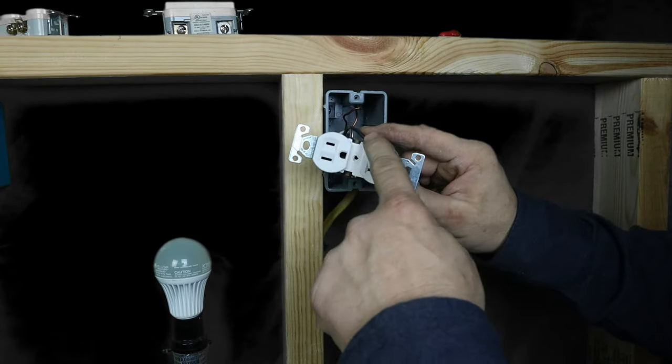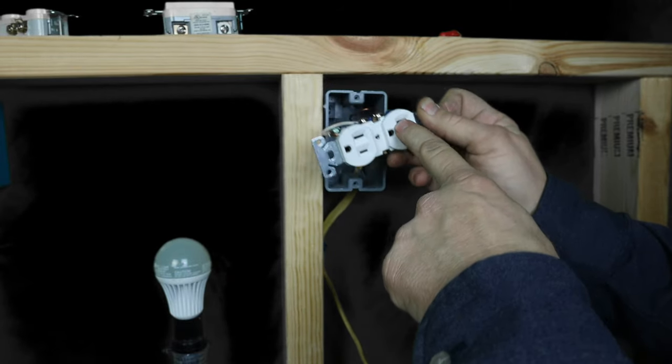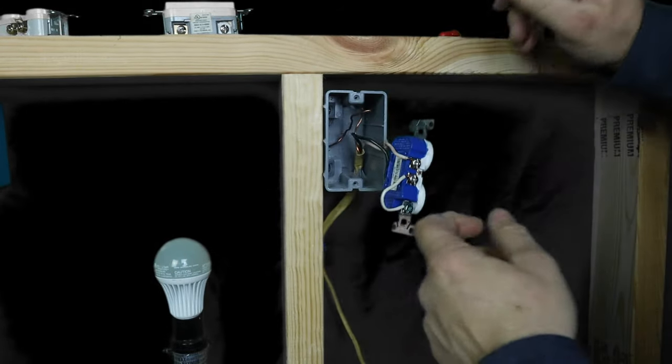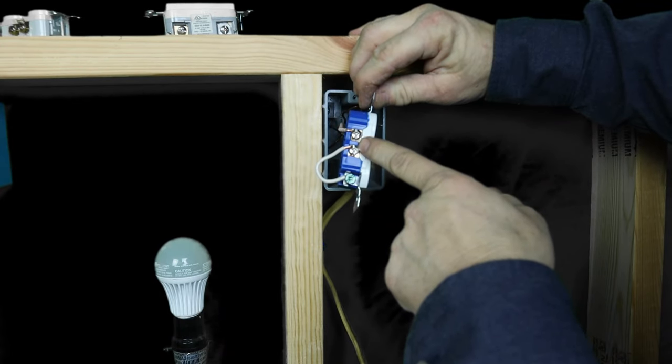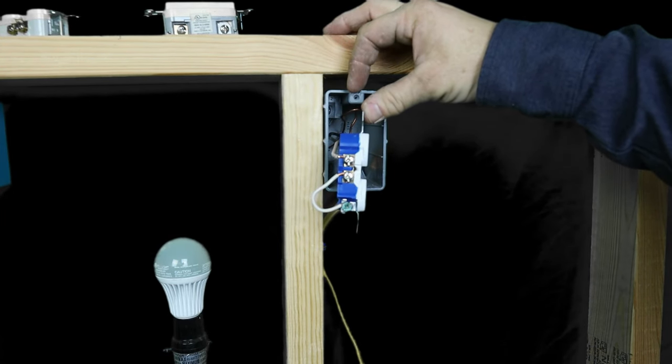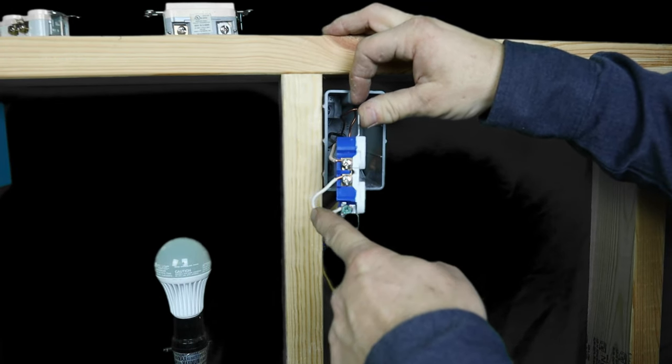So you have the hot on the right side which is good. We have the neutral on the neutral side which is good. But then what they did is they took a jumper from the neutral to the ground, which satisfied the tester and it is not right whatsoever because that is not a ground. This is just a neutral continuation. Do not do that.